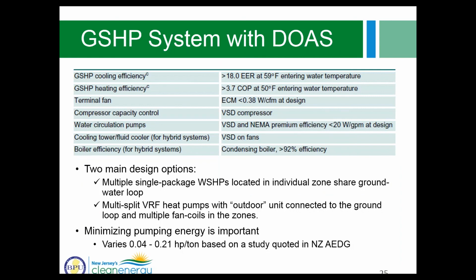Another option for HVAC system type is ground source heat pumps with dedicated outdoor air system. We don't see many projects with that system type, so hopefully there will be more in the future. So there are two main design options for this system type.